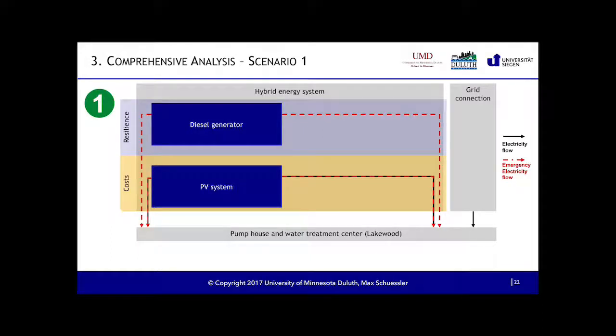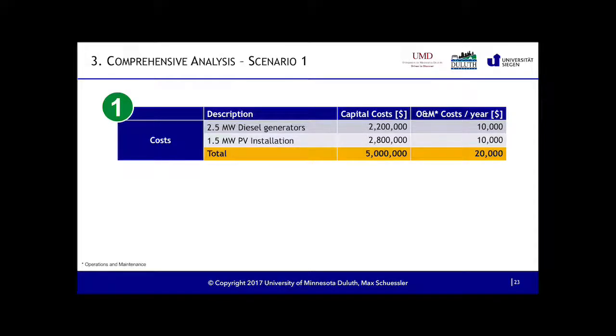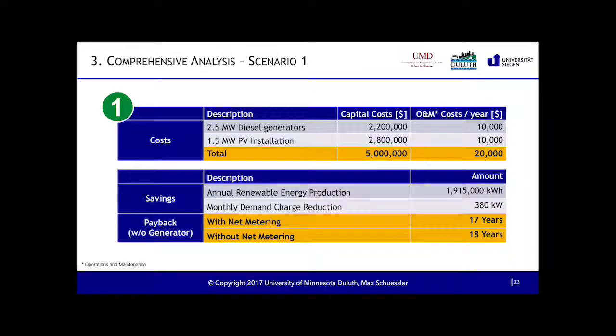So my case 1, with the 2.5 megawatt diesel generator and the 1.5 megawatt of PV, this is the total cost I will have. My capital costs, my front-end costs, will be around about $5 million and an annual charge of $20,000. But on the savings side, we would offset our 2 million kilowatt hours and probably be able to peak shave by around about 400 kW, which in the end comes down to an 18-year payback period if we don't net meter anything with Minnesota Power, which means that we do not sell our excess energy back to Minnesota Power. Net meter is not the right term for it, but to net it out. If we had this agreement, so that we don't have excess energy at all, the payback period would be down to 17 years.